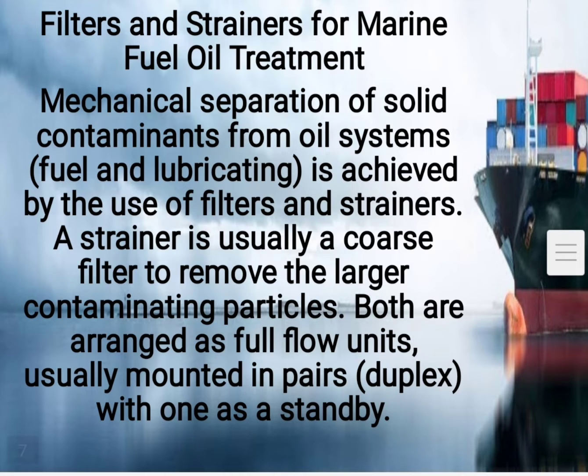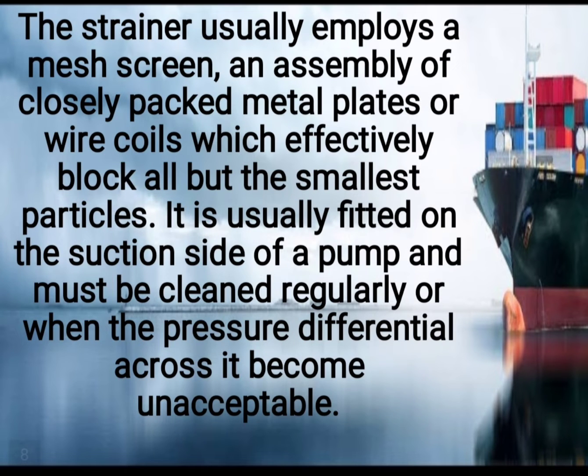Marine fuel oil filter treatment: the mechanical separation of solid contamination from oil systems, fuel and lubrication, is achieved by the use of filters and strainers. A strainer is usually a coarse filter to remove large contamination particles. Both are arranged as full flow units, usually mounted in pairs, duplex, with one as standby. The strainer usually employs a mesh screen, an assembly of closely packed metal plates or wire coils which effectively block all but the smallest particles.